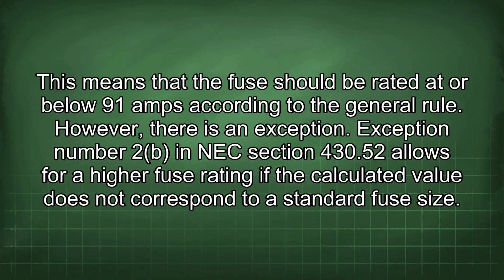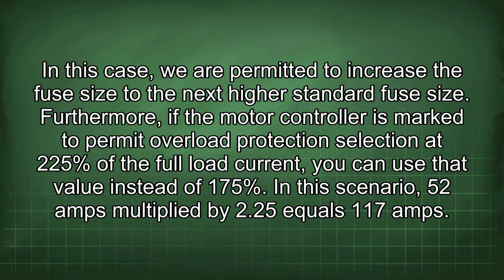However, there is an exception. Exception number 2 in NEC section 430.52 allows for a higher fuse rating if the calculated value does not correspond to a standard fuse size. In this case, we are permitted to increase the fuse size to the next highest standard fuse size. Furthermore, if the motor controller is marked to permit overload protection selection at 225% of the full load current, you can use that value instead of 175%. In this scenario, 52 amps multiplied by 2.25 equals 117 amps.